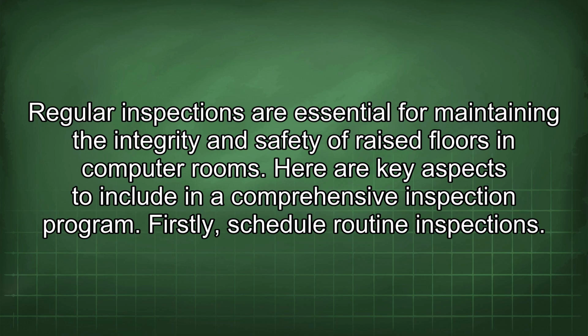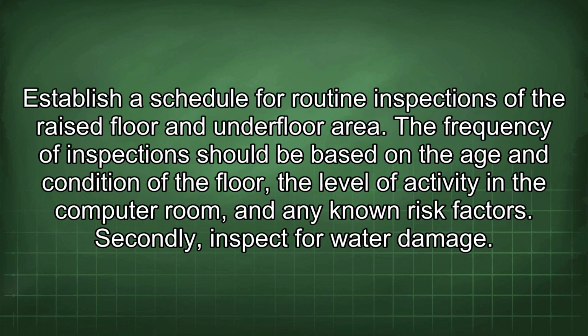Regular inspections are essential for maintaining the integrity and safety of raised floors in computer rooms. Here are key aspects to include in a comprehensive inspection program. Firstly, schedule routine inspections. Establish a schedule for routine inspections of the raised floor and underfloor area. The frequency of inspection should be based on the age and condition of the floor, the level of activity in the computer room, and any known risk factors.